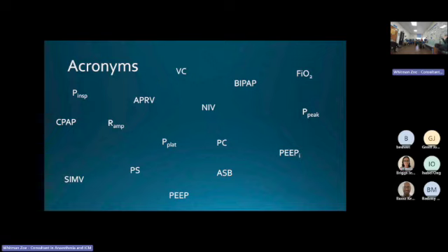Because if you think about it, you don't breathe in over 0.2 of a second. You breathe in over about a second normally. So they're getting hit in the face by air and find it really difficult. If you can slow it down so that all the pressure doesn't hit them all in one go, they find it much easier to tolerate a lot of the time. And people who wouldn't tolerate a mask suddenly find, oh, actually, that's not so bad. It's a very simple thing, but it makes sense if you think about it and understand.